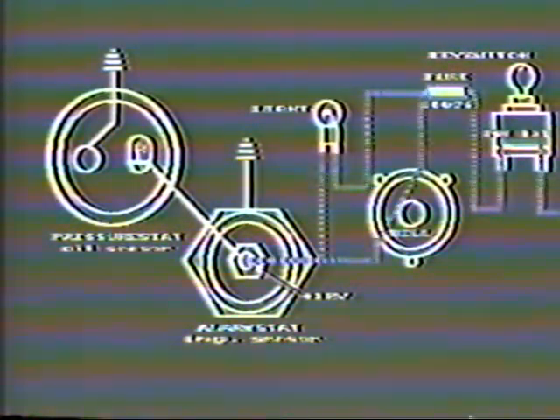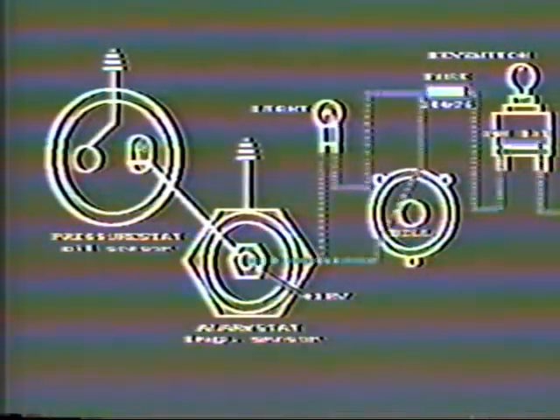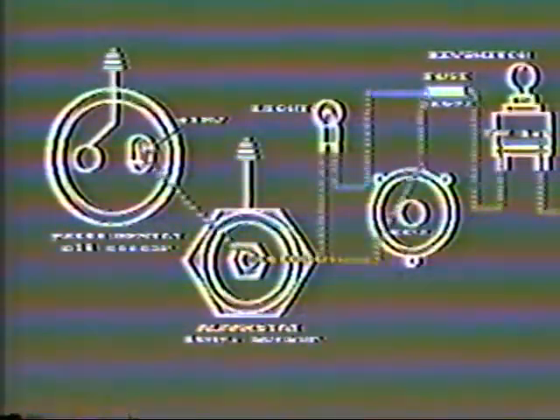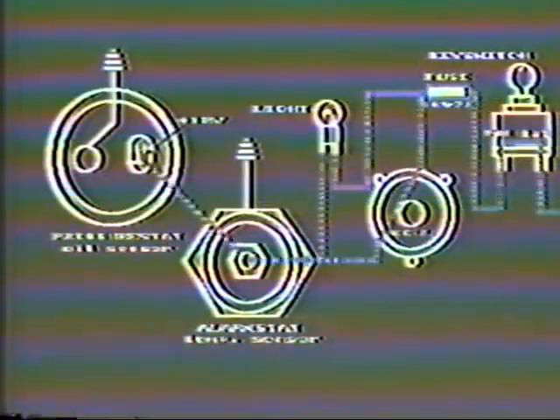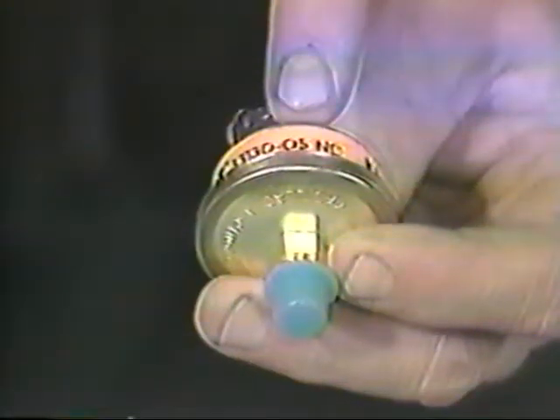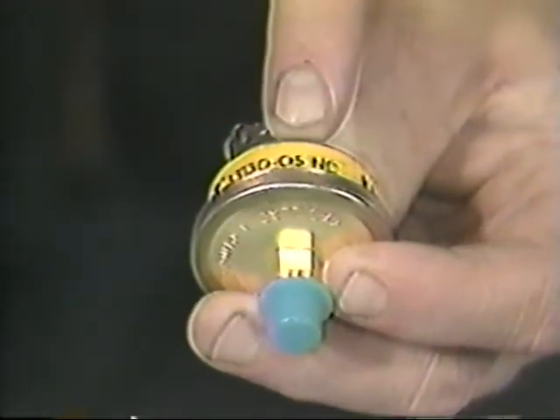The ground sides of the light and bell are wired together and connected to the alarm stat so that 12 volts is also present at this point. The final system wire connects the alarm stat and pressure stat together, so there is 12 volts present at the pressure stat. The pressure stat is normally closed, and this one is set at 5 pounds.